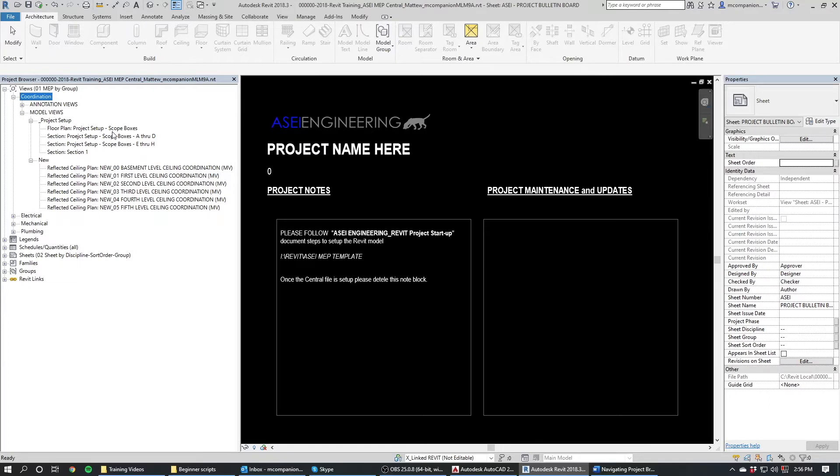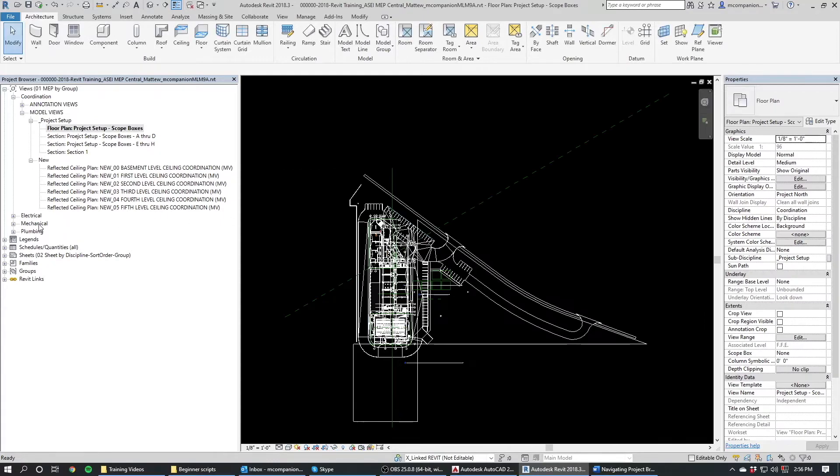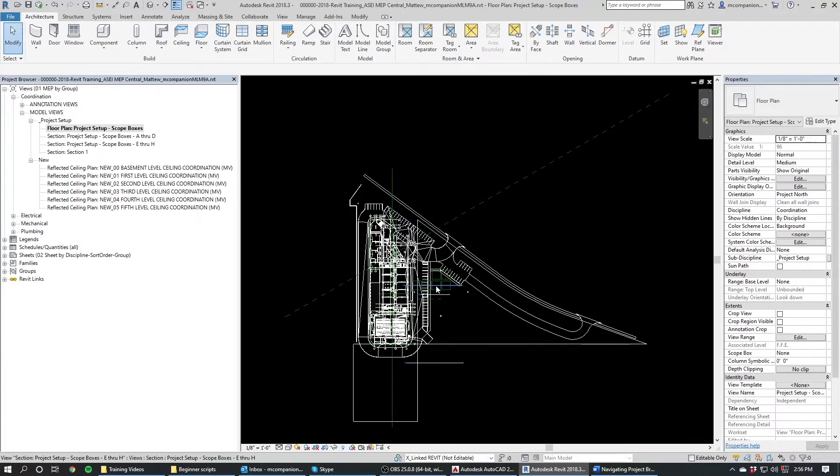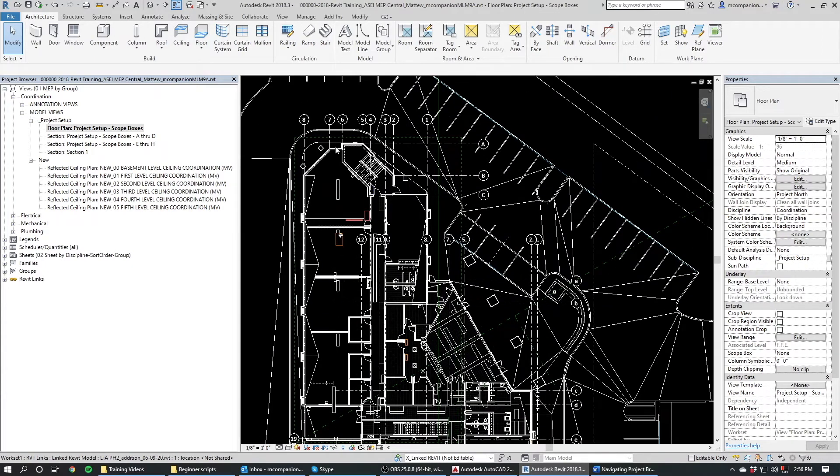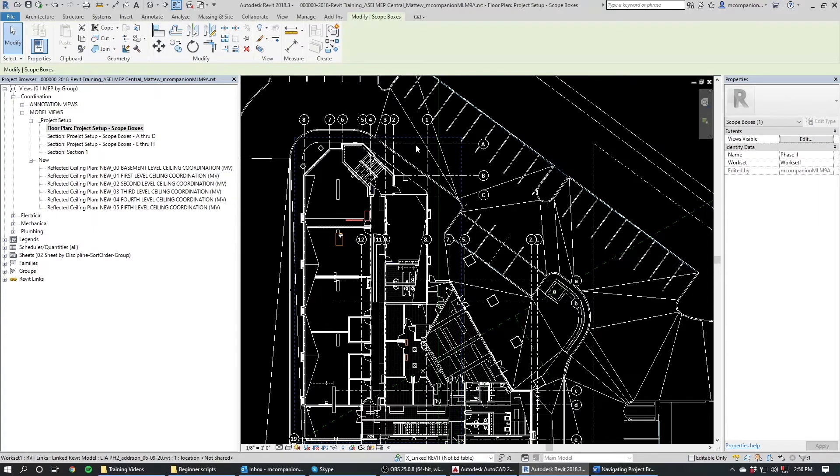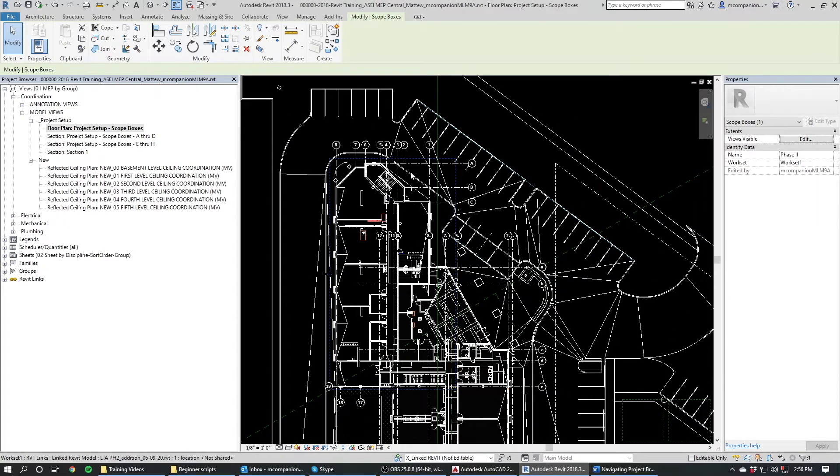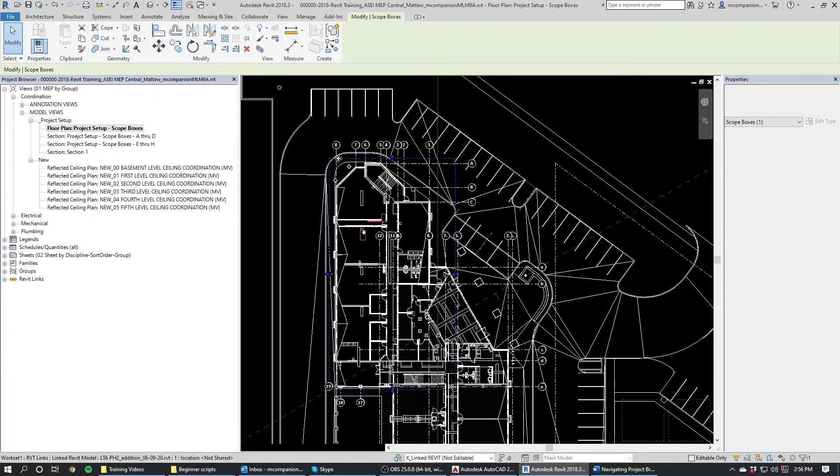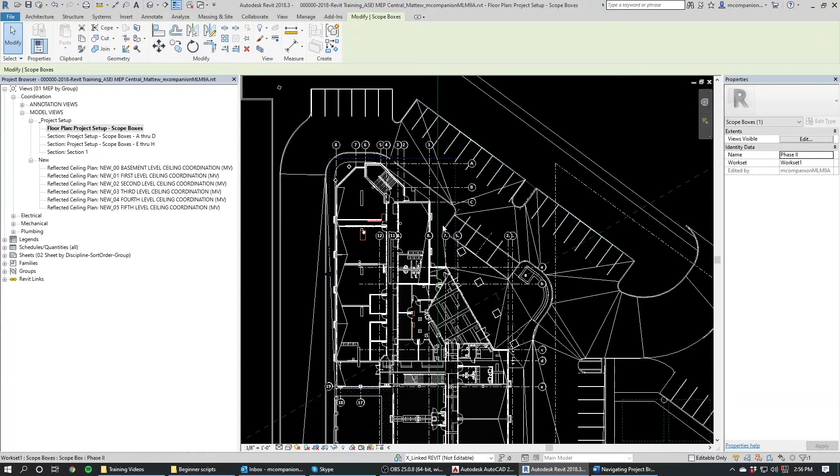But even so, even getting into an already set up project, the scope box may not be exactly what you want it to be. The scope box is what dictates what your view cut is going to be. So this is the entire model. So that's the site. We've got all this extra site work out here that we don't want to see. We don't need to see. Our scope of work is this little chunk of this building right here. So we take this one scope box, we drag it over here, we name it phase two. So now we've got a scope box and then in all of our subsequent electrical, mechanical and plumbing views, we would reference those views to phase two.